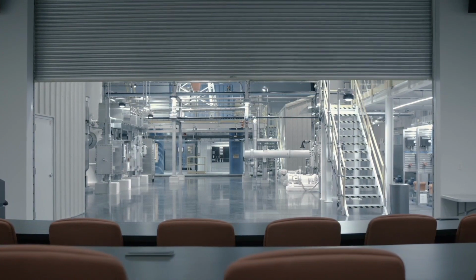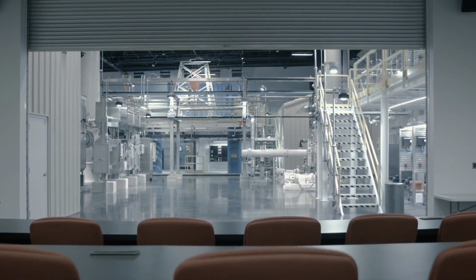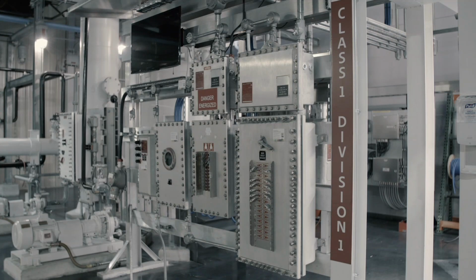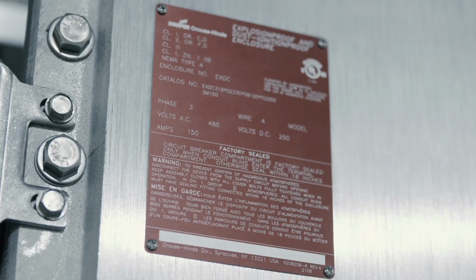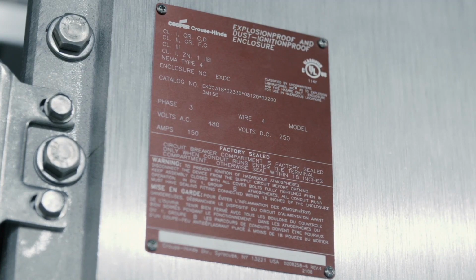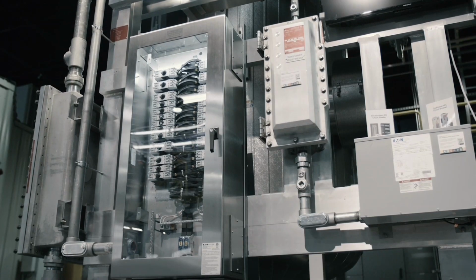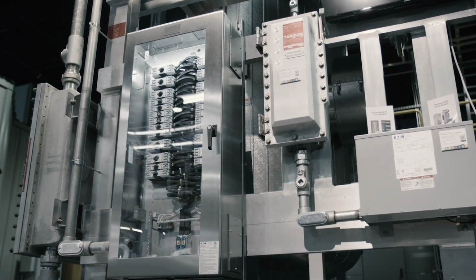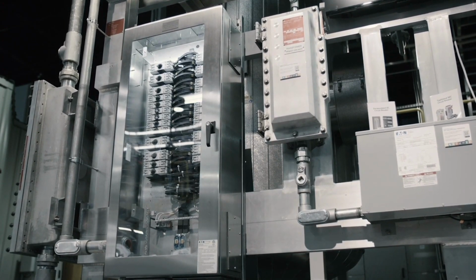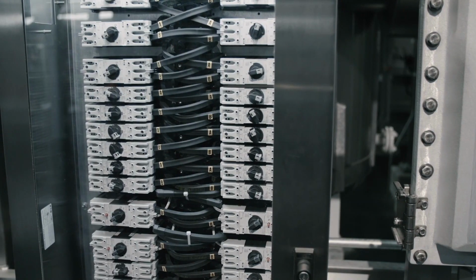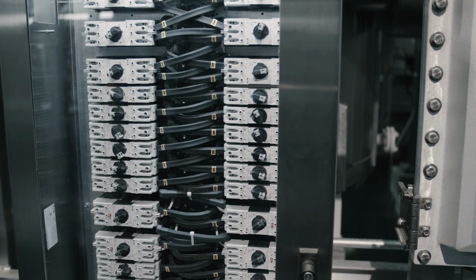Here in the Houston Power Systems Experience Center, we've replicated a HAZLOC application to assist in training and education. For this video, it also allows us to show design differences between classified locations. For example, this cast panel board is rated for Class 1 Division 1 and is what we call an explosion-proof enclosure. This enclosure, on the other hand, is rated for a Class 1 Division 2 area, which allows us to use a stainless steel enclosure with encapsulated breakers.